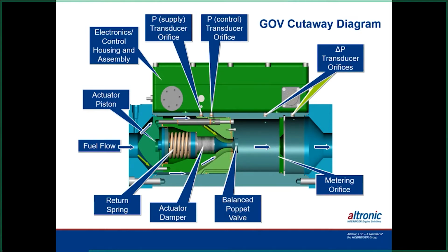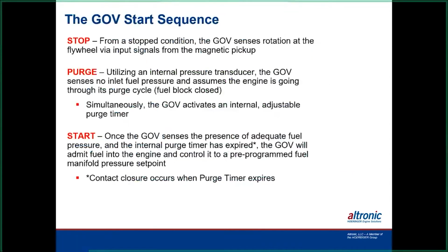Depends on how clean the gas is, or the air. Starting sequence in a stop condition: the engine will sense rotation of the flywheel, input of the mag pickup, and then we'll go through, like I said earlier, with the purge cycle. It will run on a timer for so many RPM, making sure it purges the engine of any fuel that may have leaked into it.